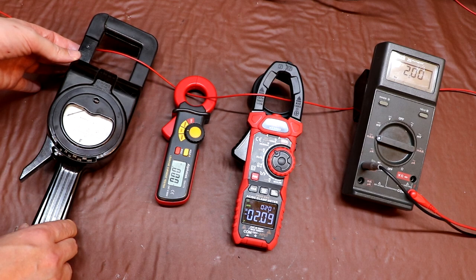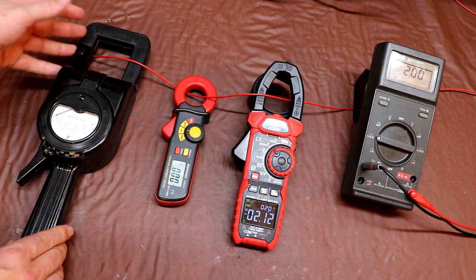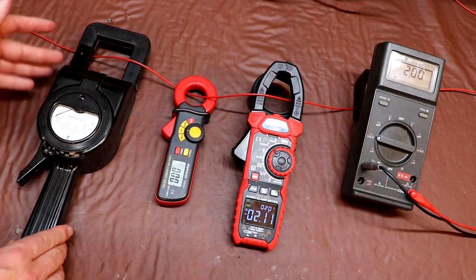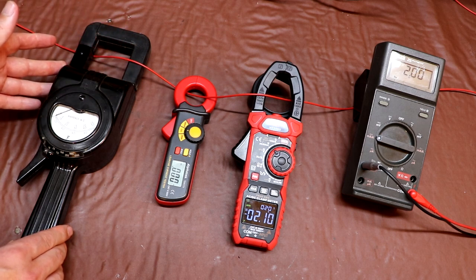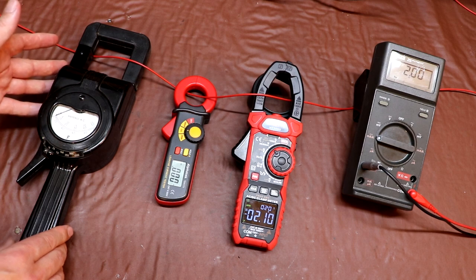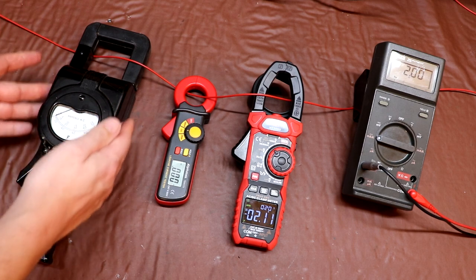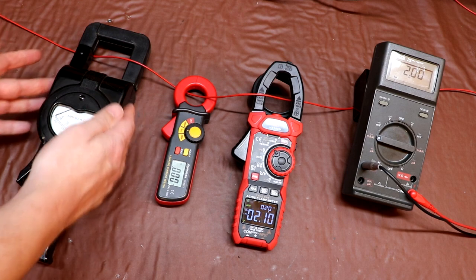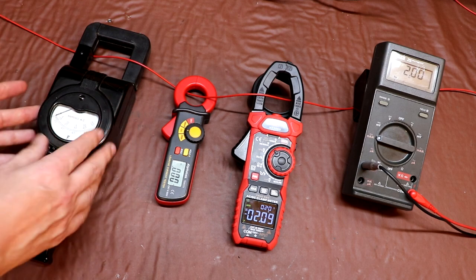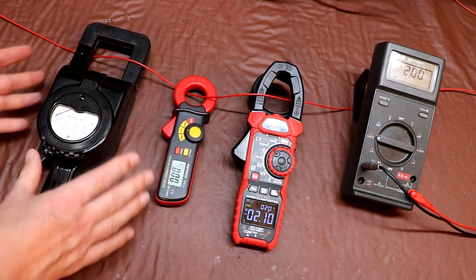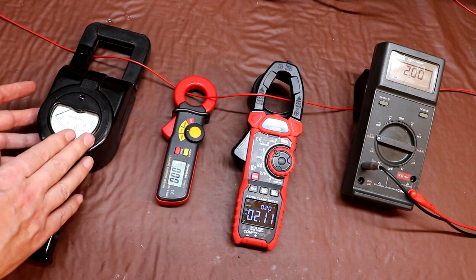You need to pass AC through them for them to work, because if you just put DC through them, what will happen is the actual core within the transformer will become magnetised, it will saturate with DC, and you won't actually get any transfer of magnetic flux between the primary and the secondary side, so the meter movement won't operate. So these are AC reading meters only.